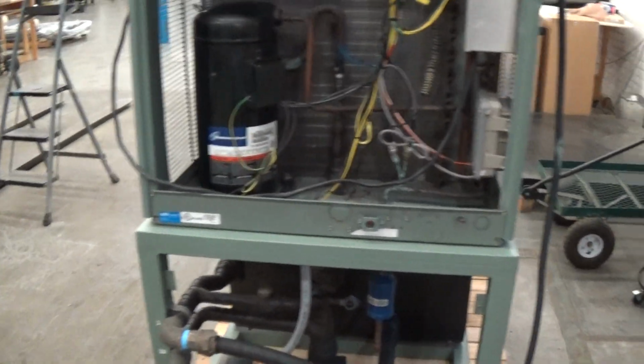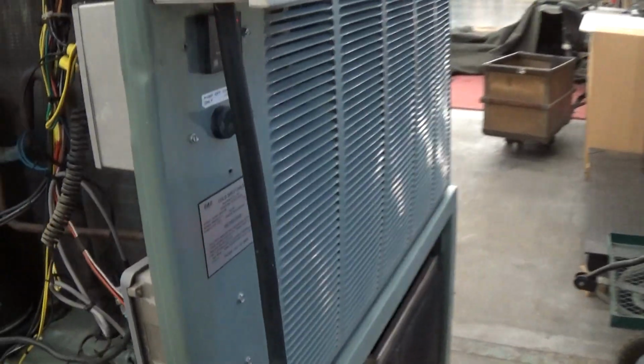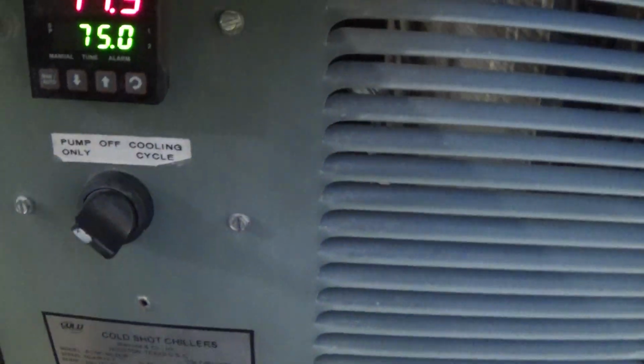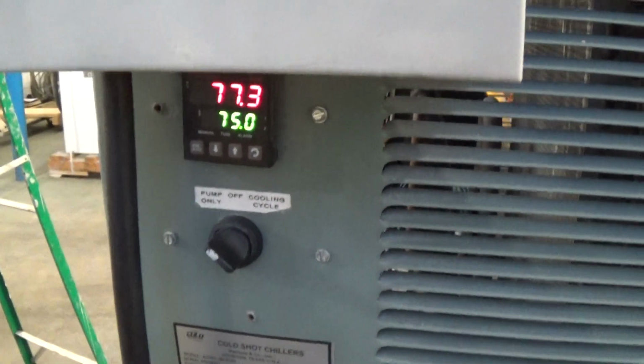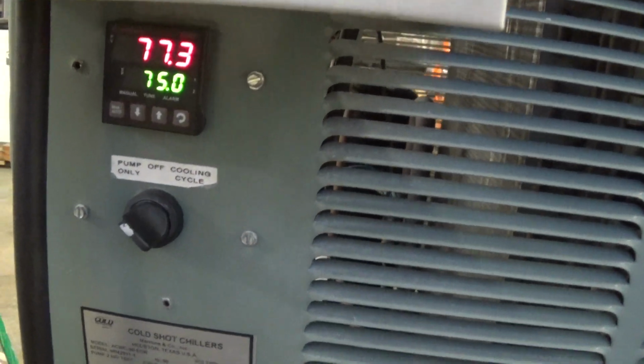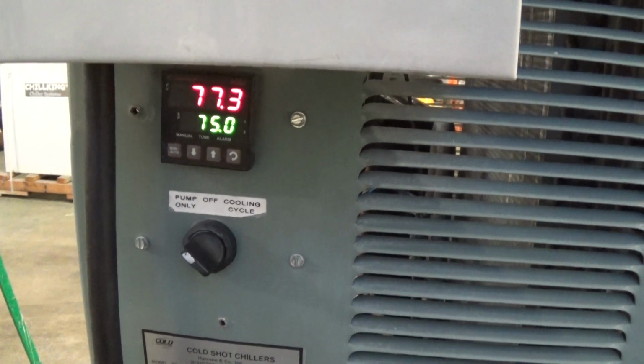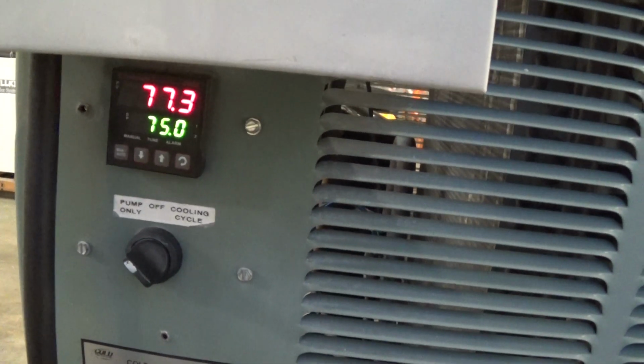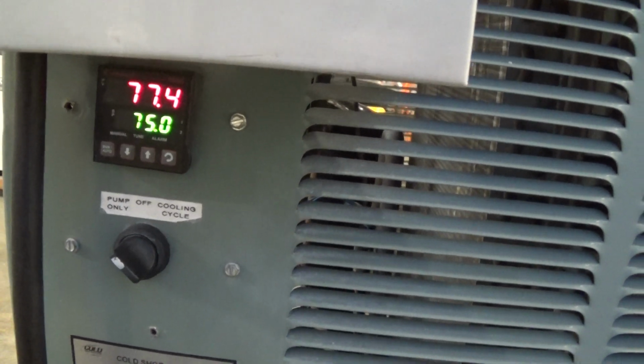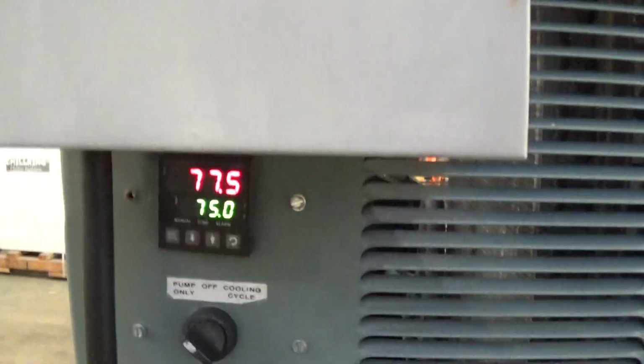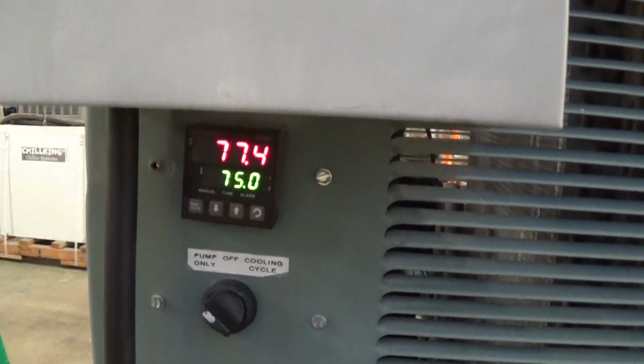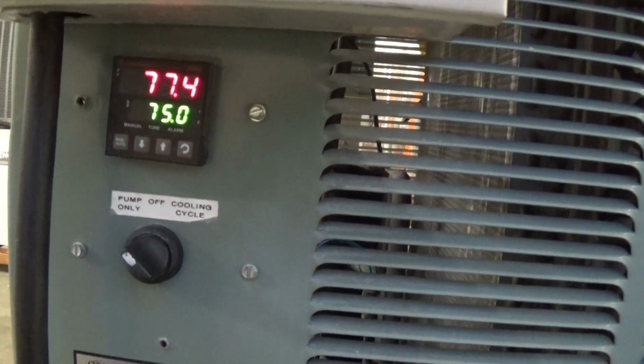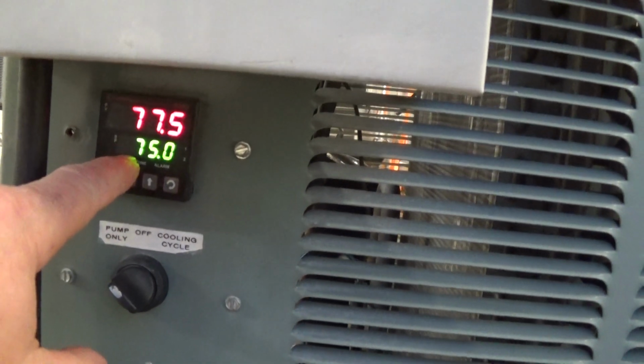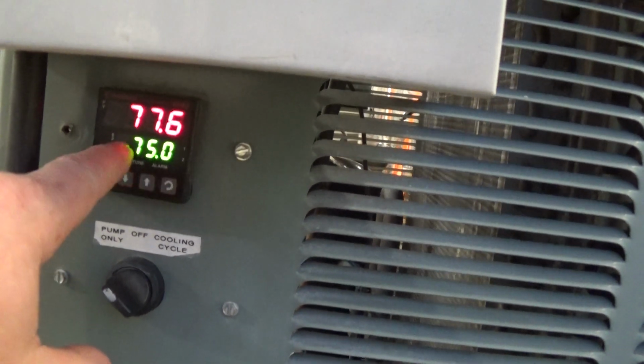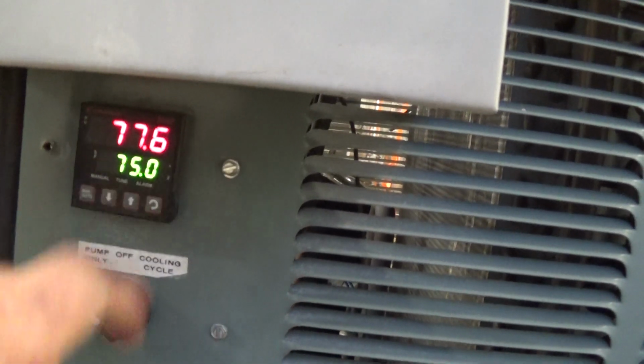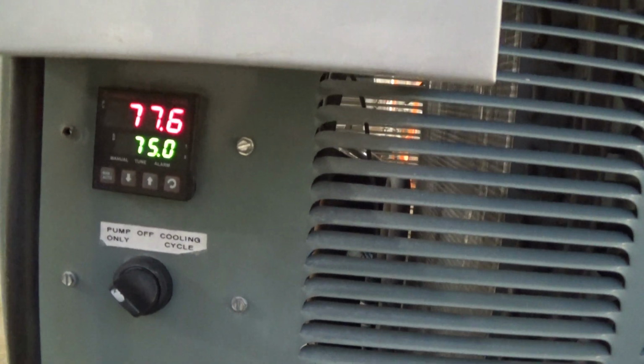So we're running the pump a little bit right now. I'm just going to go ahead and start chilling and talk about a few other things while it happens. For our test, and we've tested it extensively, we simply fill up the tank, create a little loop, and let it kind of heat itself up. It heats itself up eventually just through the friction of flow and the pump itself. Down here, this shows you SP, that's our set point. The red shows you what the current value is.